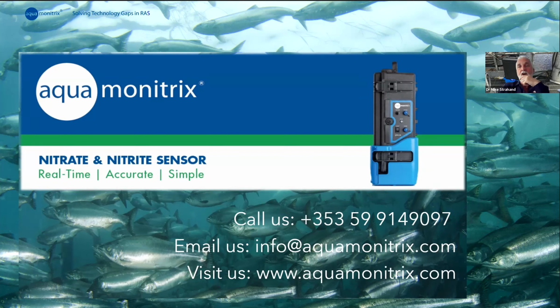Can we measure nitrite and nitrate in aeration basins? Absolutely, definitely. And we will be running a webinar on our applications in activated sludge, Sheena. But the answer to your question is yes, we have got excellent data even in the aeration basins, and we're working on greenhouse gas reduction and energy optimization in that area.